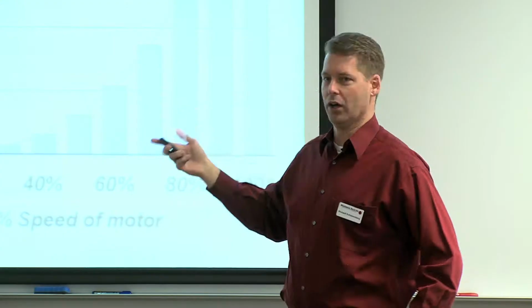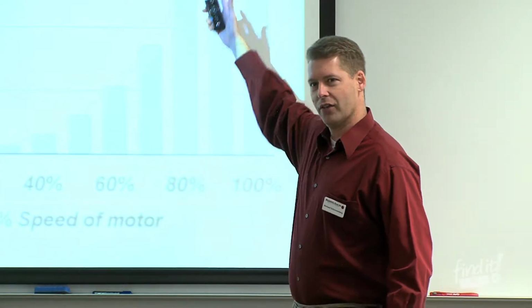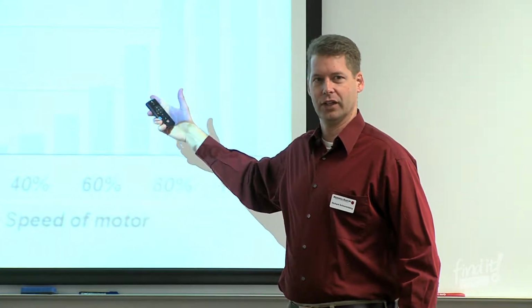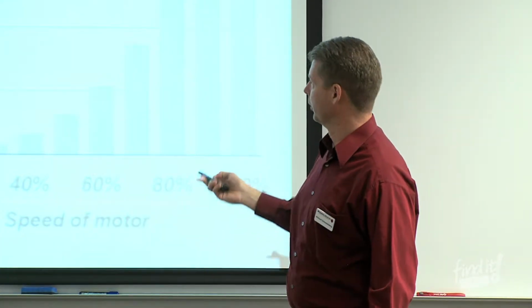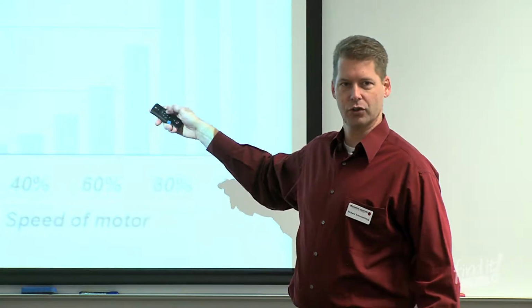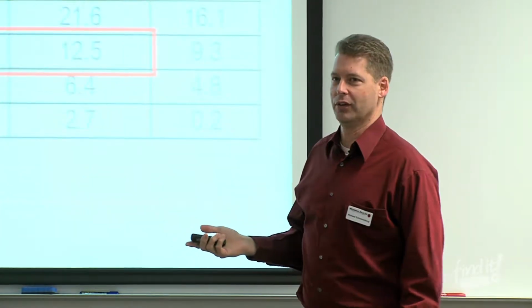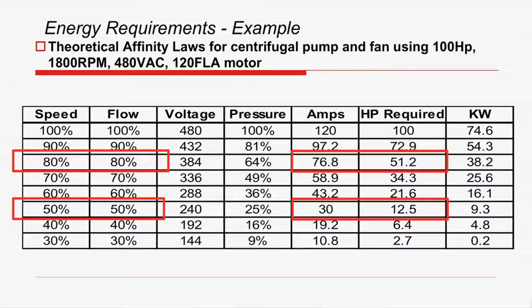So with the affinity laws, we can save a lot of energy by slowing down the flow rate of the VFD and slowing the flow rate of your system down just a little bit. So this is a nice pretty chart. It shows something, but it works a lot better, it seems, in tabular form, so I'm producing that same chart as a table for you and highlighting a couple of things, like at 80% flow, 80% speed.